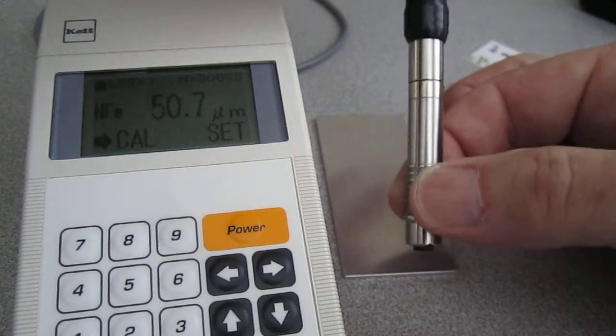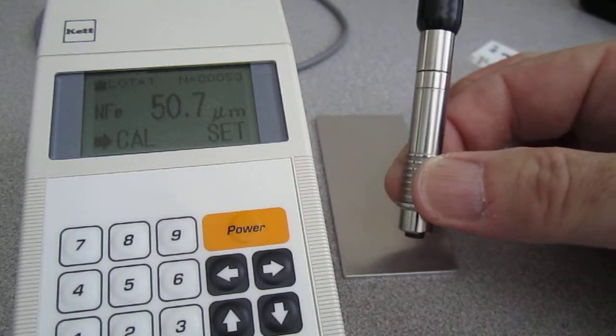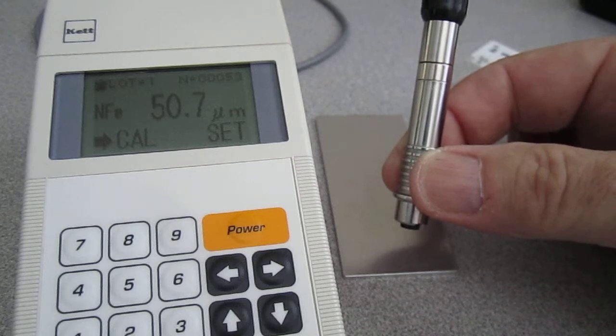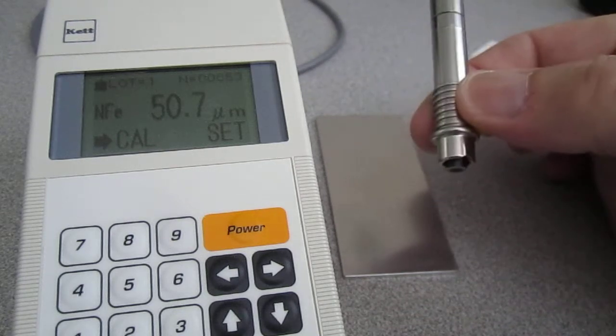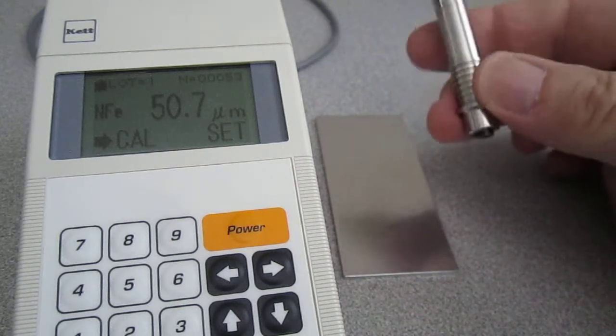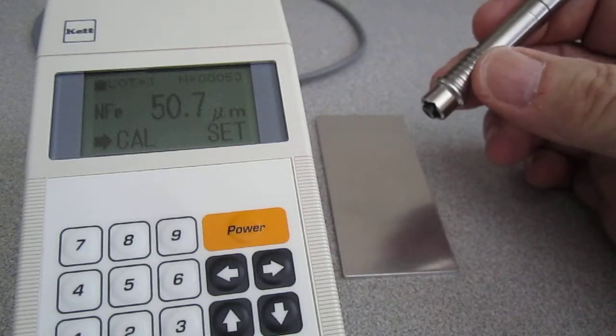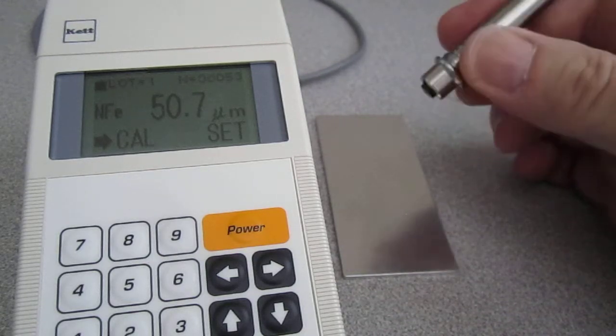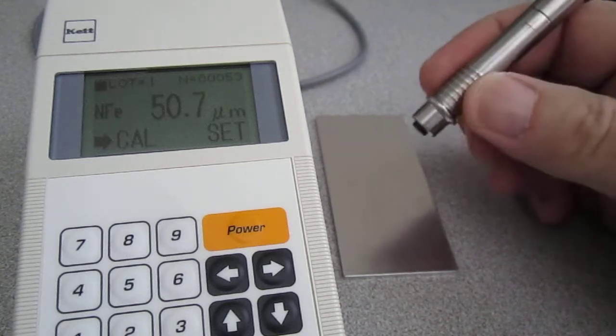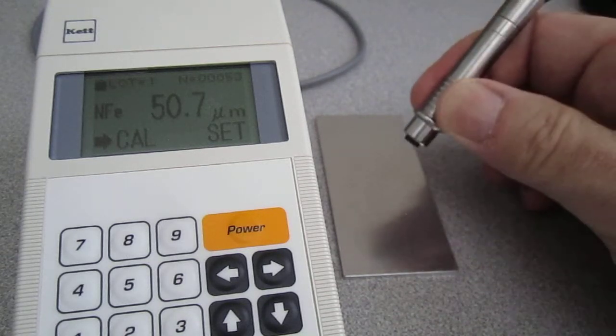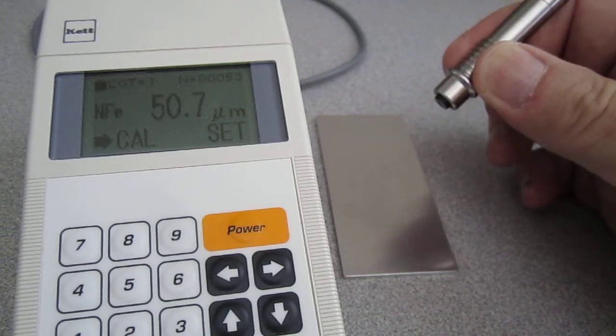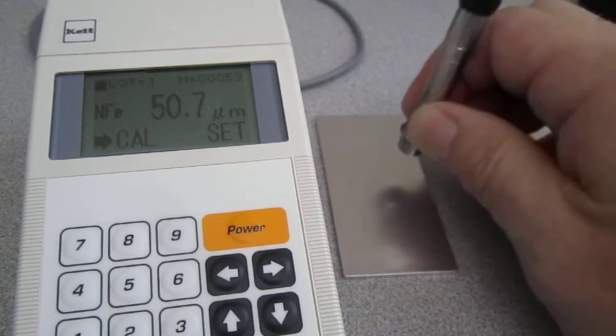You'll notice that the probe is spring-loaded to give consistent pressure and therefore help the operator make a consistent measurement. You'll also notice that the edge where the operator would hold the probe has both an extrusion portion and rough edges, which make it easier in a humid or damp environment to hold it or a hot environment to hold it and make good contact. We try to make it easy for the operator to get good measurements.